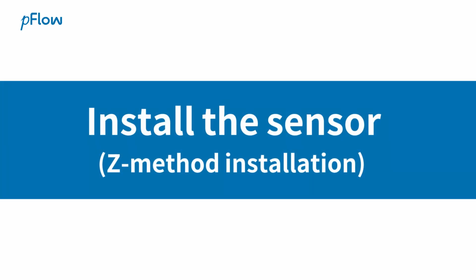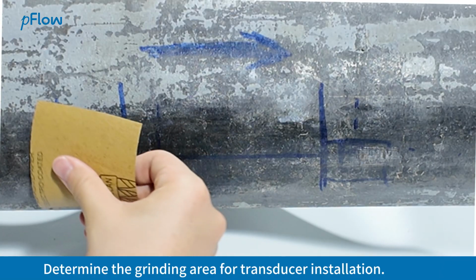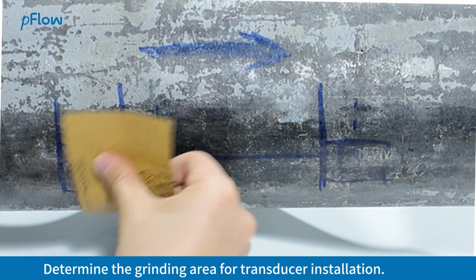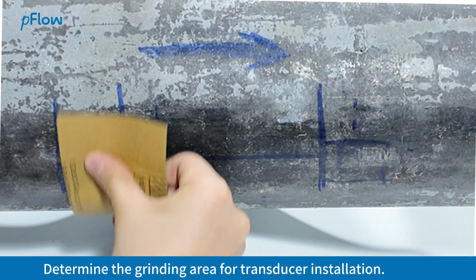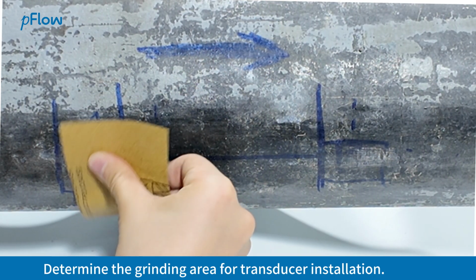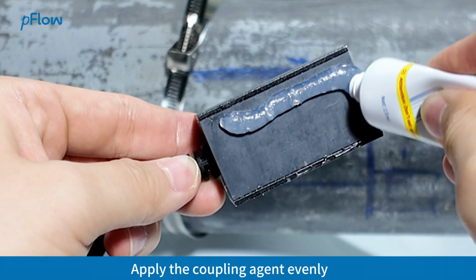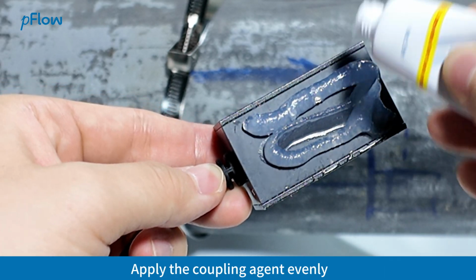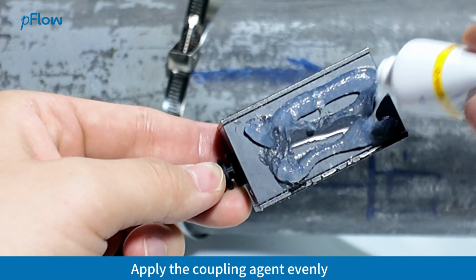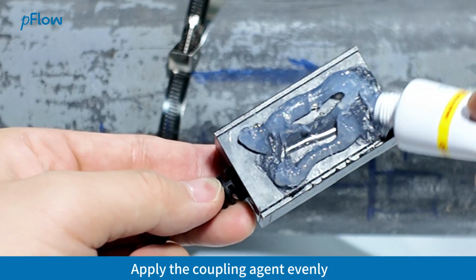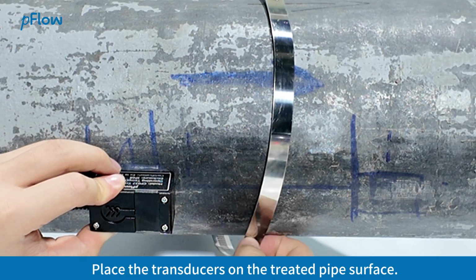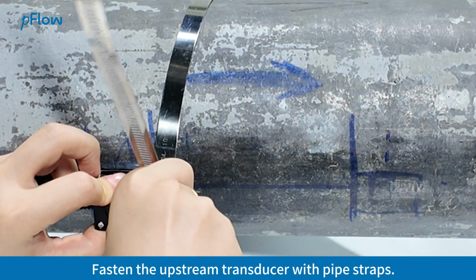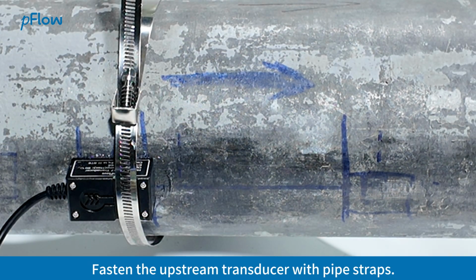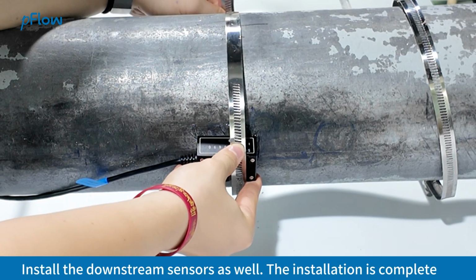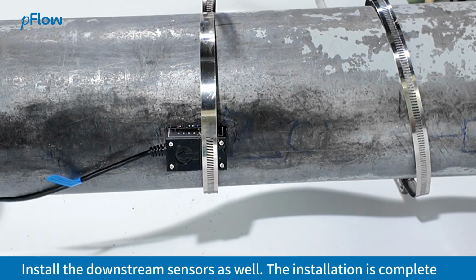Install the sensor. Z method installation. Determine the grinding area for transducer installation. Apply the coupling agent evenly. Place the transducers on a treated pipe surface. Fasten the upstream transducer with pipe straps. Install the downstream sensors as well. The installation is complete.